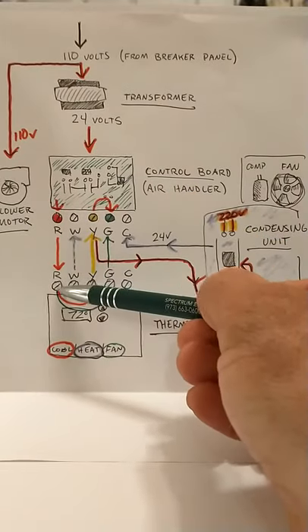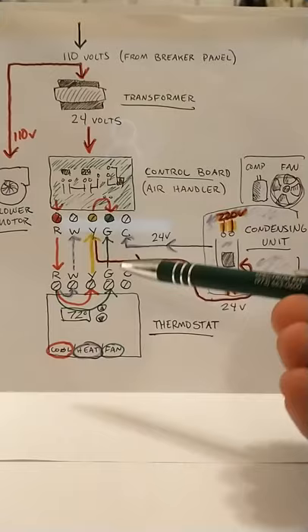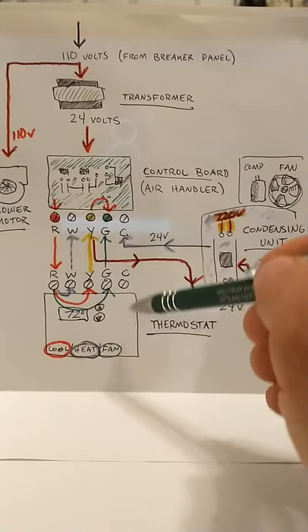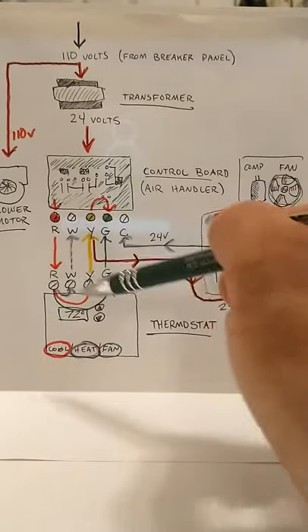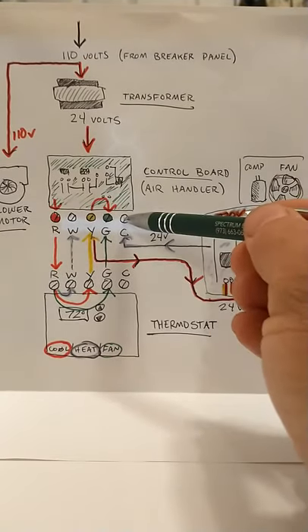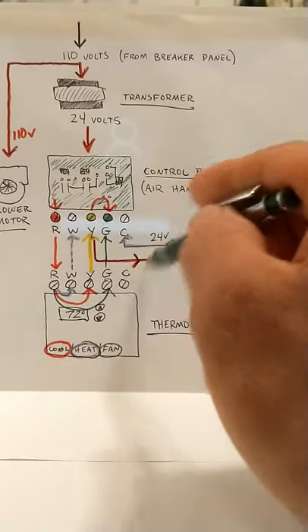So when your system is off, your 24 volts kind of stops right there and it doesn't really go anywhere. Sometimes you might have a thermostat that actually runs off of 24 volts instead of batteries. So you will have a blue wire, for example, going for your common at your thermostat to your common at your air handler, and that's just the 24 volts that the thermostat itself runs off of.